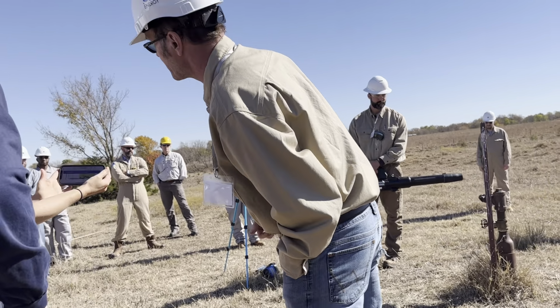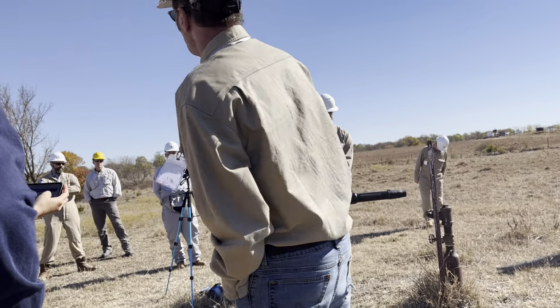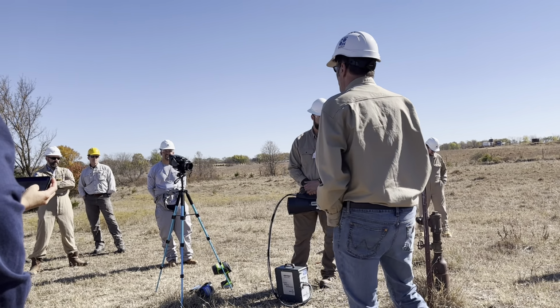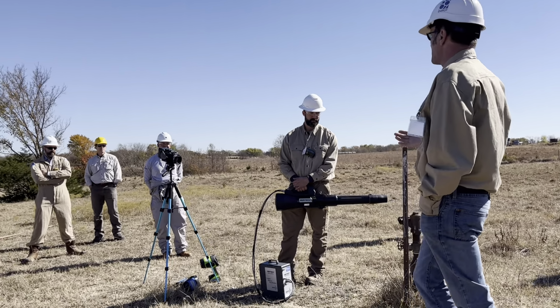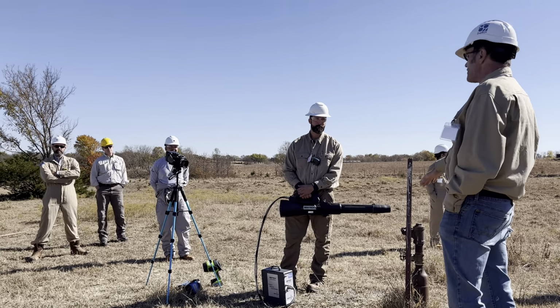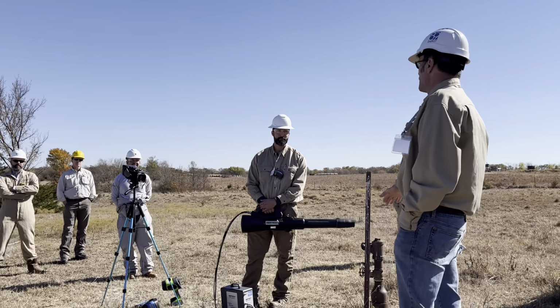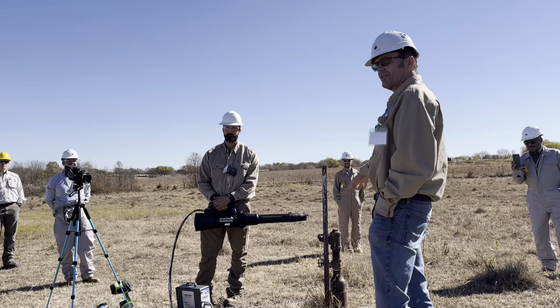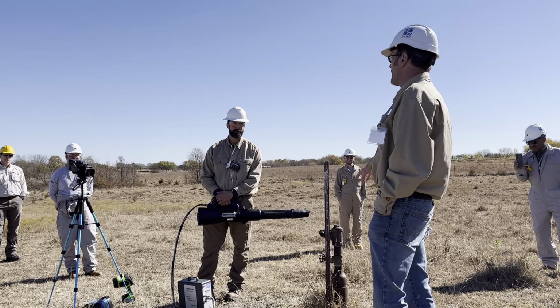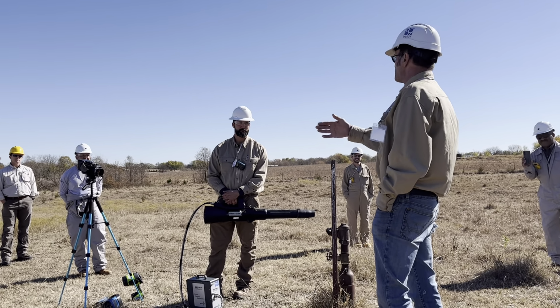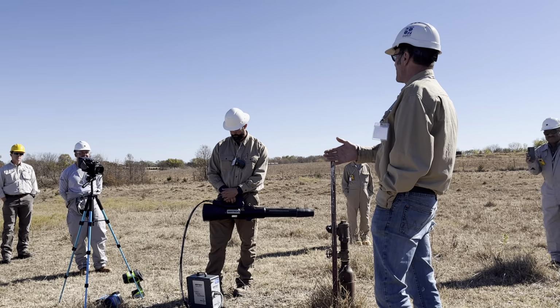What's it say now? It went down to 3 ppm. Well, 3 ppm between friends is not a lot of leak, right? And even this very small leak went up to 400 ppm. So we could go down an order of magnitude without any problem.